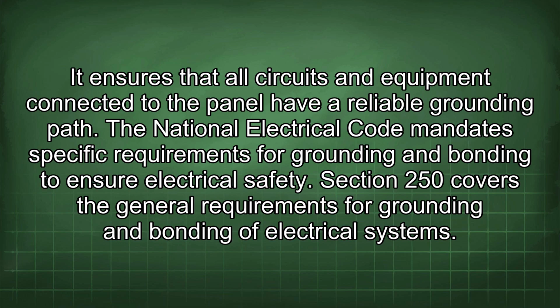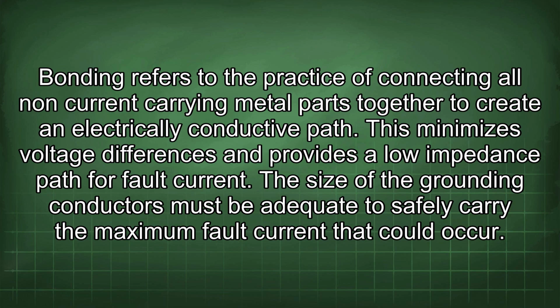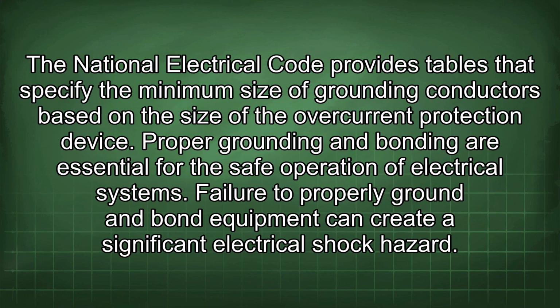The National Electrical Code mandates specific requirements for grounding and bonding to ensure electrical safety. Section 250 covers the general requirements for grounding and bonding of electrical systems. Bonding refers to the practice of connecting all non-current carrying metal parts together to create an electrically conductive path. This minimizes voltage differences and provides a low impedance path for fault current. The size of the grounding conductors must be adequate to safely carry the maximum fault current that could occur. The National Electrical Code provides tables that specify the minimum size of grounding conductors based on the size of the overcurrent protection device. Proper grounding and bonding are essential for the safe operation of electrical systems.